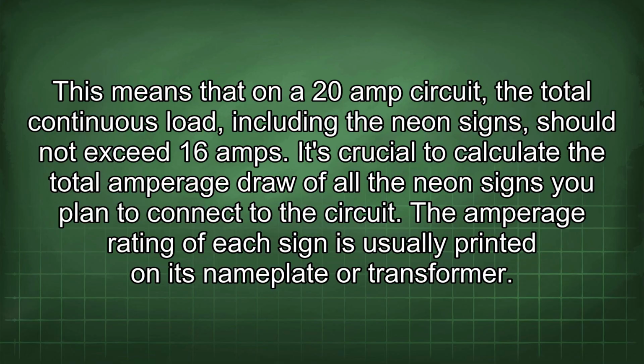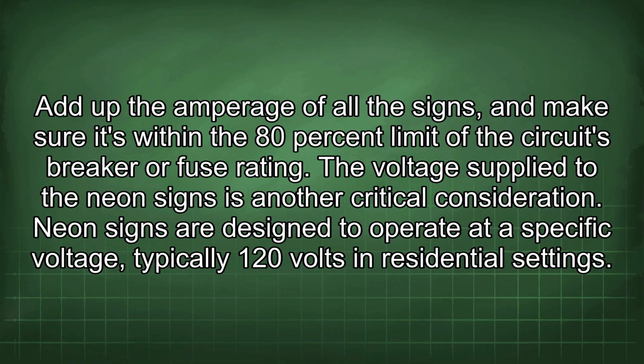amps. It's crucial to calculate the total amperage draw of all the neon signs you plan to connect to the circuit. The amperage rating of each sign is usually printed on its nameplate or transformer. Add up the amperage of all the signs, and make sure it's within the 80% limit of the circuit's breaker or fuse rating.